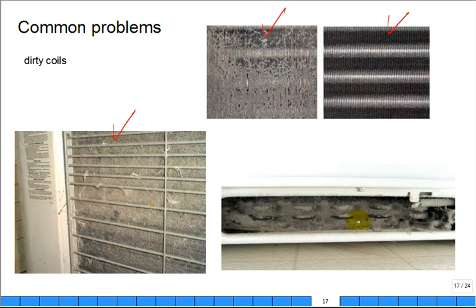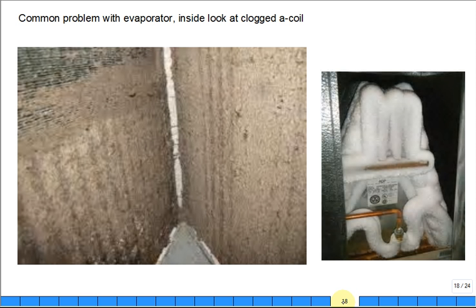Here is a peek underneath the refrigerator in somebody's house. Take the front grill off. Take a look. This is supposed to be the condenser coil. It's all clogged up with dirt. You think airflow's good over that? Guess what your refrigerator in your house looks like? Maybe like that.